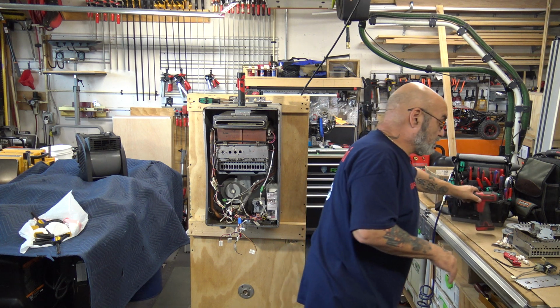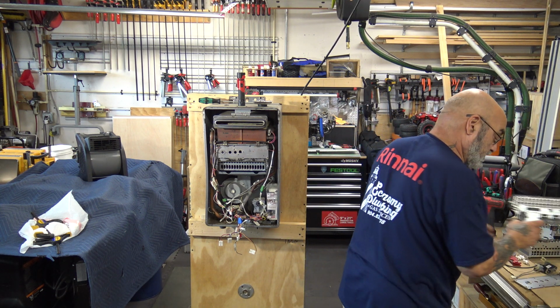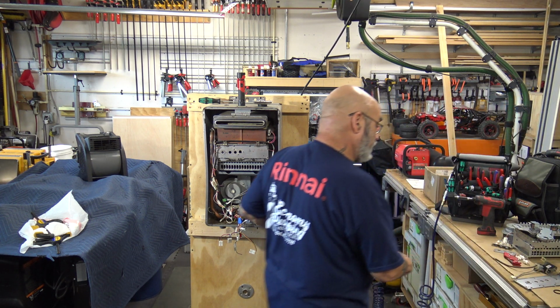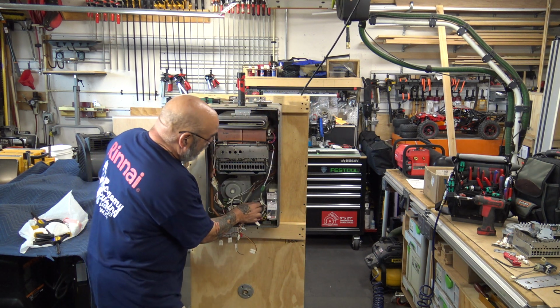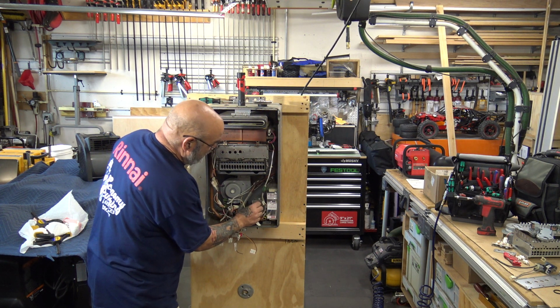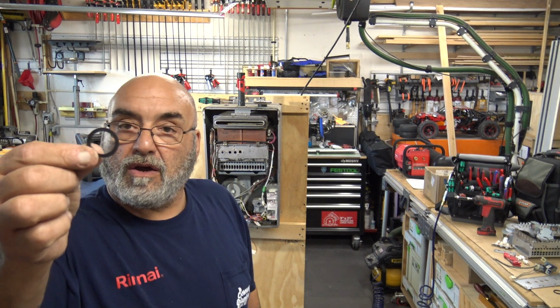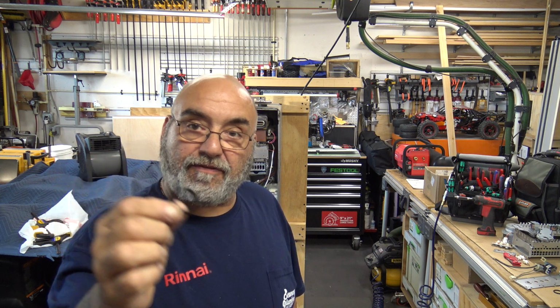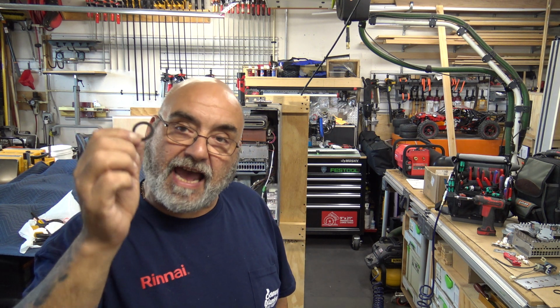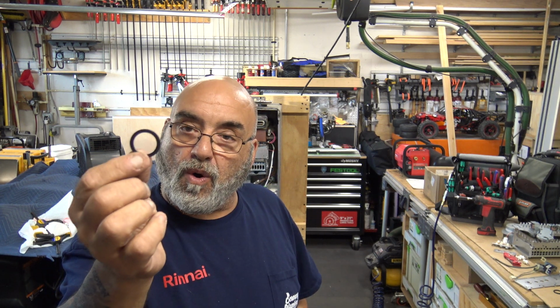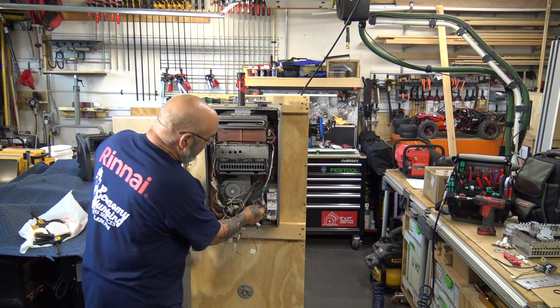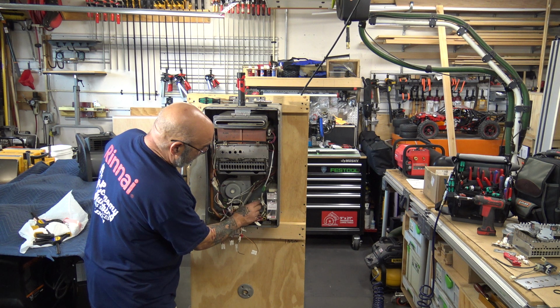Now we got to put the big screws in. Now, here's something important. You got to make sure that the flat O-ring for the gas valve stayed in. It's also good to have these extra. So if you're going to order O-rings, like for the heat exchanger, the thermistors, order a couple of O-rings for the gas valves.